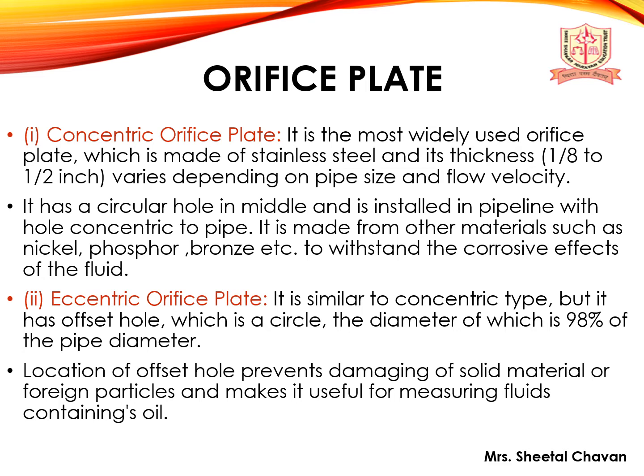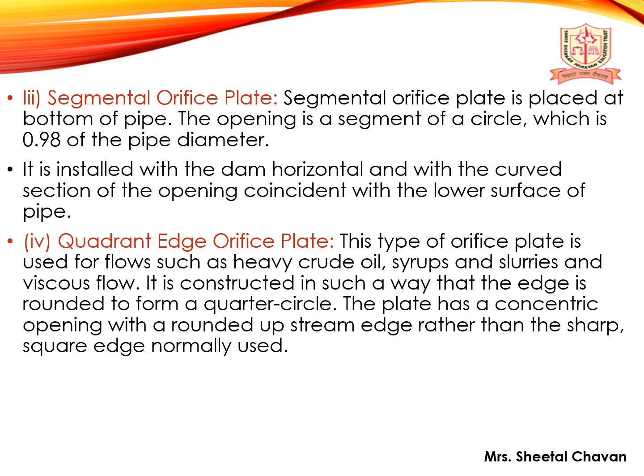The second is the eccentric orifice plate, similar to the concentric type but with an offset hole whose diameter is 98% of the pipe diameter. The offset hole prevents damage from solid or foreign particles and makes it useful for measuring fluids containing oils. The third is the segmental orifice plate, placed at the bottom of the pipe. The opening is a segment of a circle with a diameter 0.98 of the pipe diameter, installed with the curved section coincident with the lower surface of the pipe.